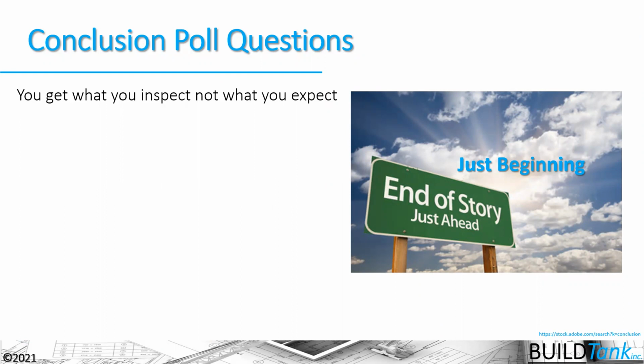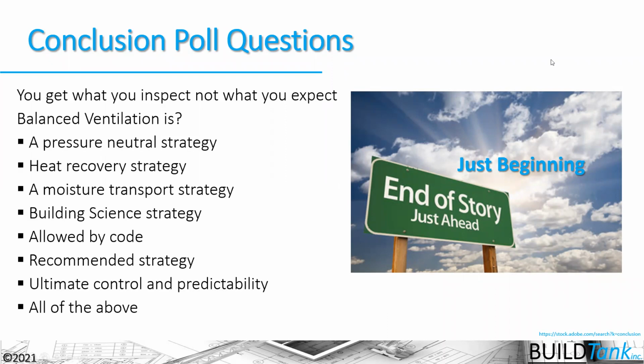So, to conclude from my perspective here, balanced ventilation is the ideal ventilation strategy that we want to use in our houses. The other strategies work, and they're very installation specific in terms of climate and how they're installed. All of these systems have to be inspected because, again, you get what you inspect, not what you expect. But balanced ventilation is a pressure neutral strategy. So we have less concern about combustion safety and health and safety issues, and less concern about the moisture content in that air, being able to recover that moisture content if we want to, and to recover that energy if we want to. So most of the people are getting what I'm talking about from a balanced ventilation strategy. And although the code doesn't require you to do it, it's the strategy of choice for folks out there.